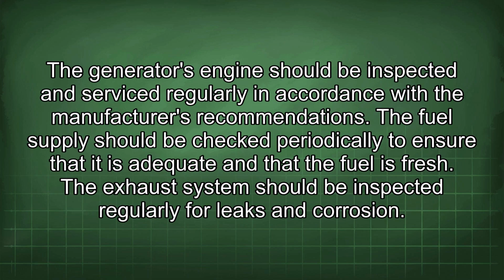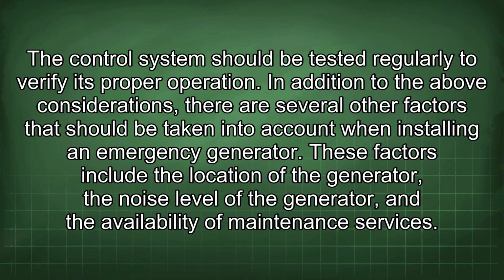The generator's engine should be inspected and serviced regularly in accordance with the manufacturer's recommendations. The fuel supply should be checked periodically to ensure that it is adequate and that the fuel is fresh. The exhaust system should be inspected regularly for leaks and corrosion. The control system should be tested regularly to verify its proper operation. In addition to the above considerations, there are several other factors that should be taken into account when installing an emergency generator.